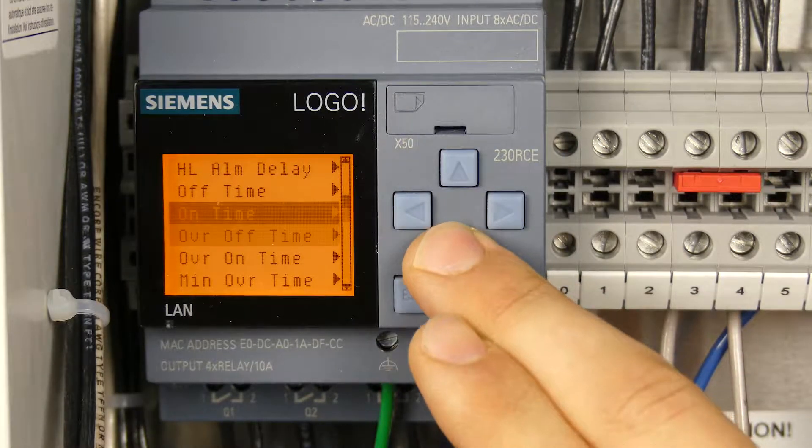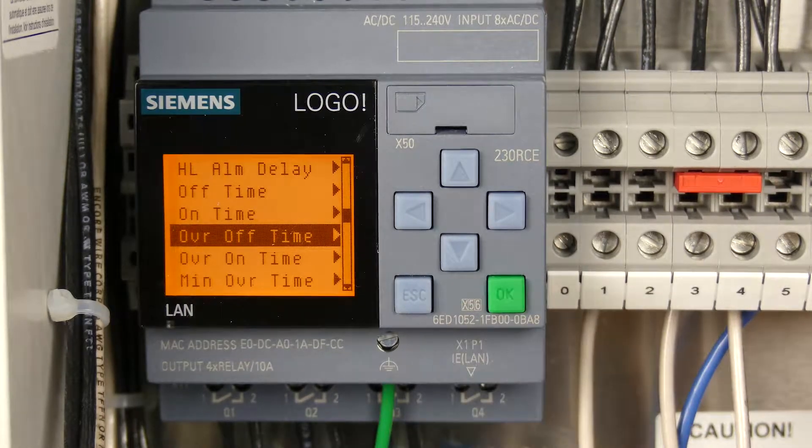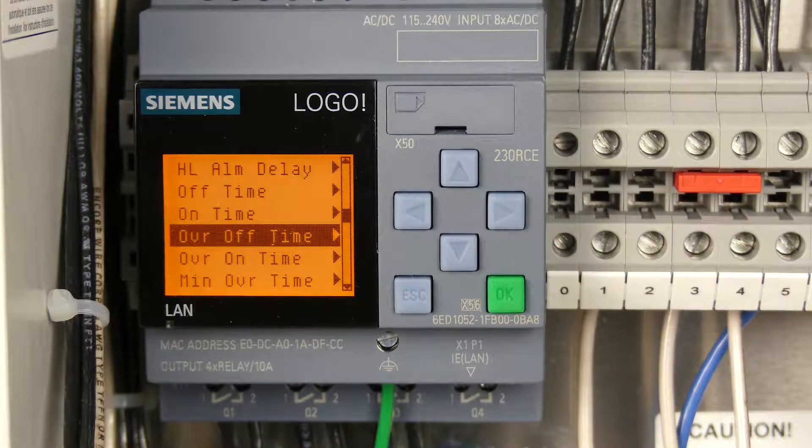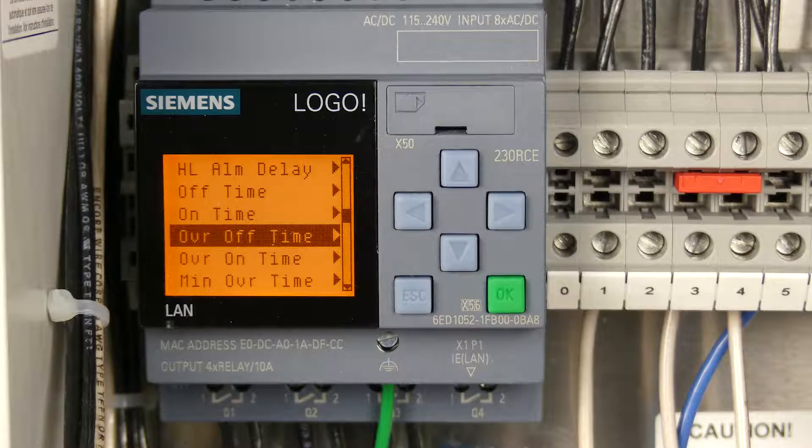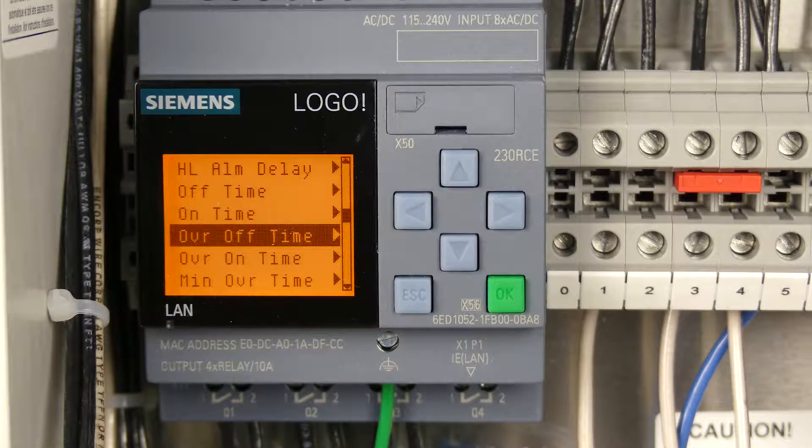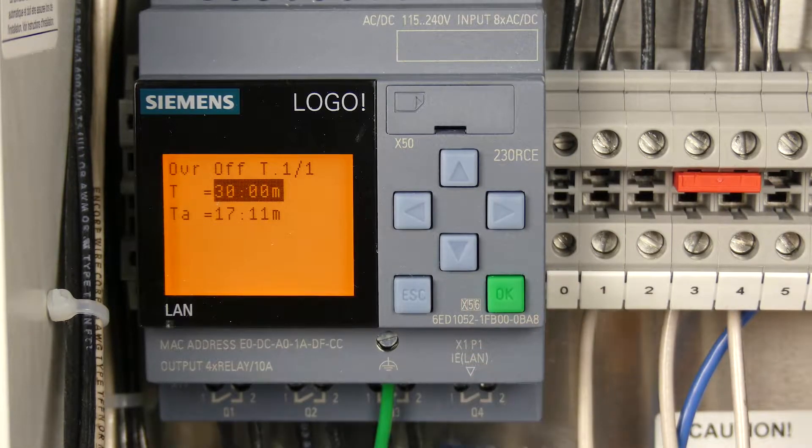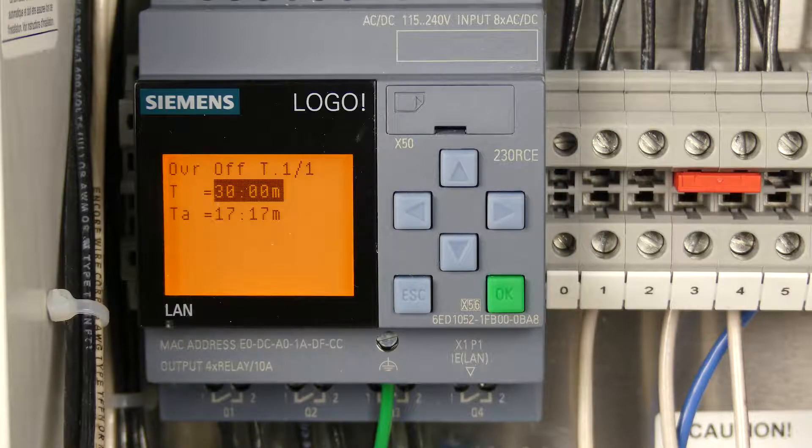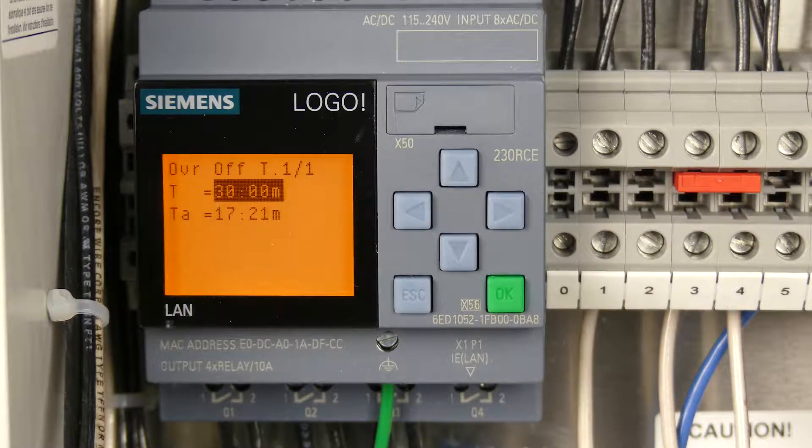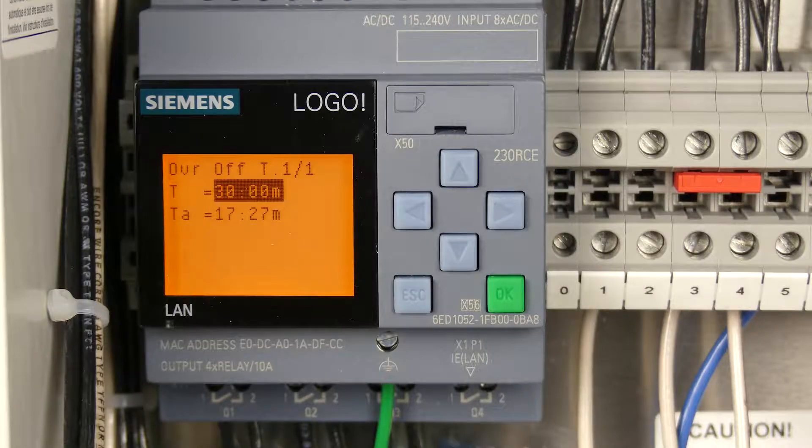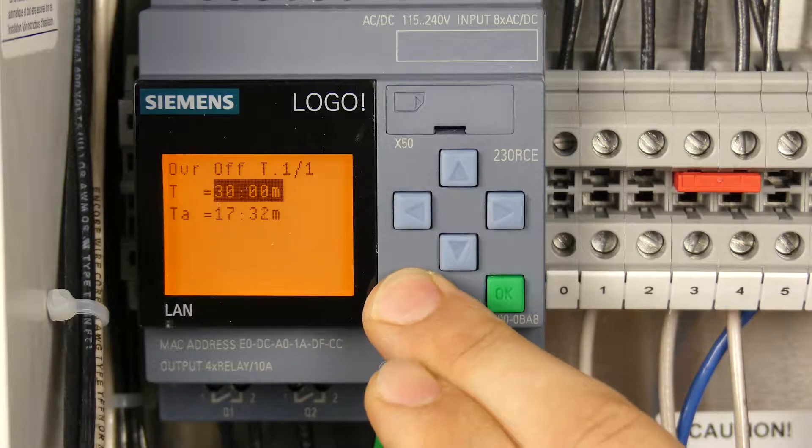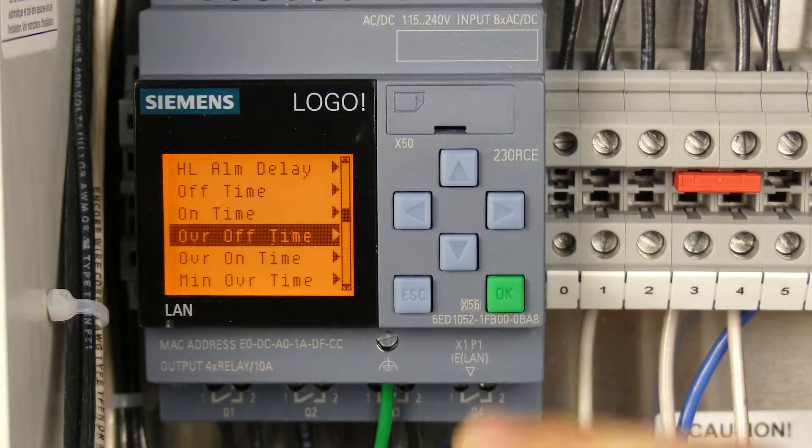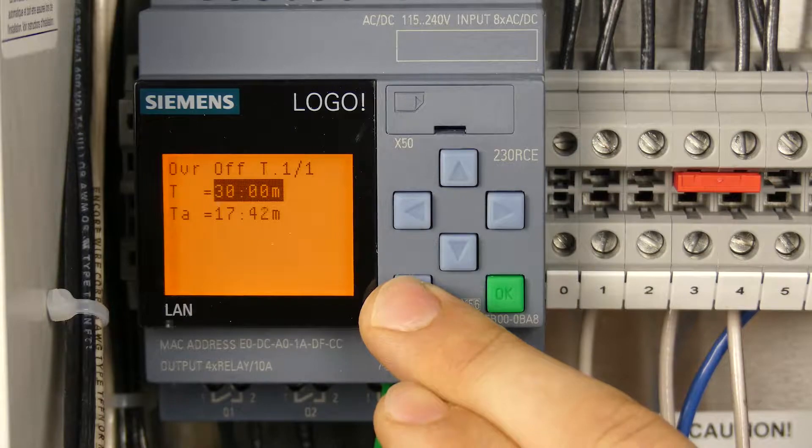Another parameter that applies to timed dose is the override timer off time. Let's talk about what override timer means in an MVP panel. You're going to have a float that indicates when the system goes into override mode, which essentially means the system is not keeping up in its standard mode. Override mode has a default off time of 30 minutes, which is essentially half the amount of time of the default off time. When the panel enters override mode, it's going to operate nearly twice as much until it gets caught back up and returns to standard operation.